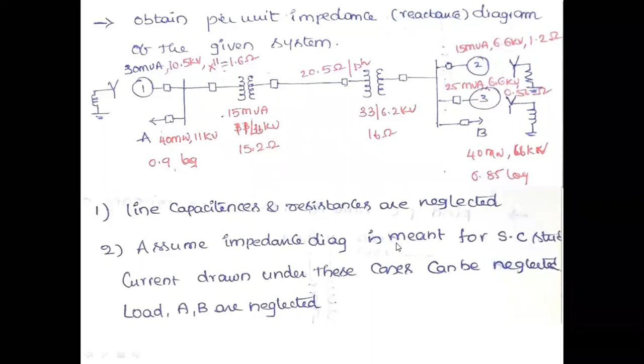So this is the problem we have solved, and for your sake, I have solved this problem step by step. Okay, first we are going to choose the proper base values. In this particular case, the generator ratings are the base values for the entire system, and the first need is to convert the ratings of transformer 1 and transformer 2. Why? Because we need to equate the operating voltage of the secondary winding of the first transformer and the primary winding of the second transformer. Whenever you equate these two voltages, obviously that is the operating voltage of the transmission line. So for that purpose, now see here, the operating voltage of the transmission line.